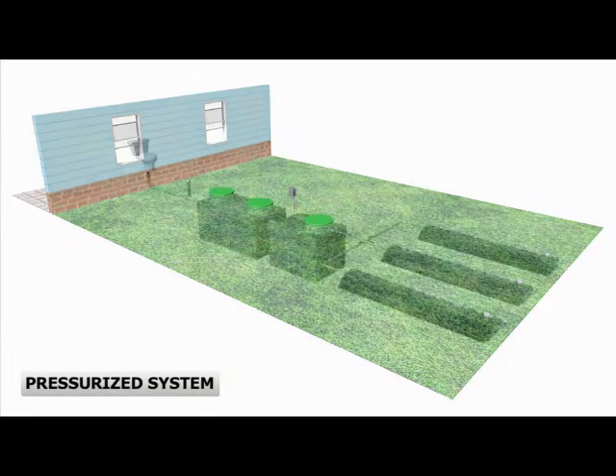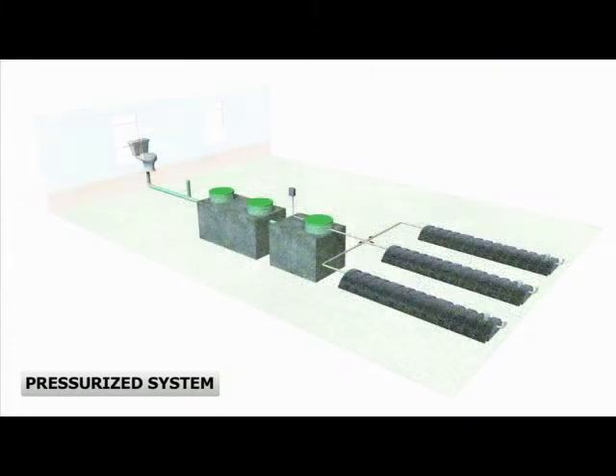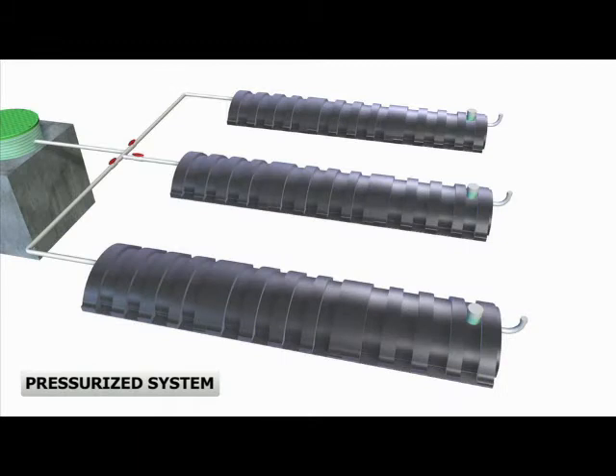A pressurized system has a second tank that houses a pump, which allows the effluent to be pumped to pressurized pipes in the drain field. The drain field starts with a manifold that splits the wastewater evenly between a series of pressurized pipes, where the effluent is distributed over the drain field area through small holes in the pipes.